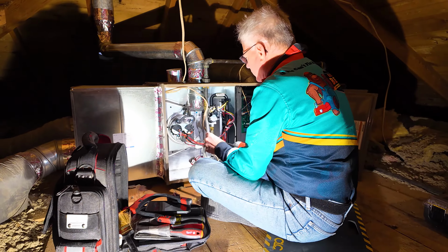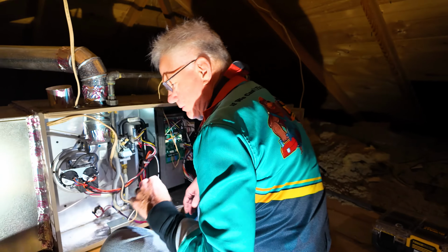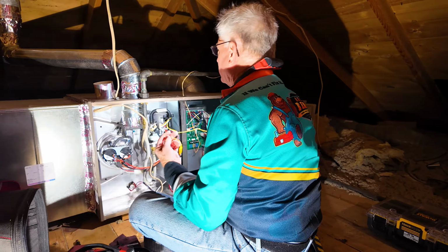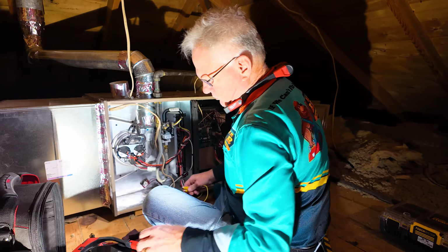Okay, so now I'm going to use a jumper like as if I turned the thermostat on downstairs. We'll see if it has a call for heat. I'm going to turn on the power to the furnace. And there's a safety switch right here, when you take the cover off, it won't run. So I have to hold that switch in. I have a magnet situation that I use here when I'm doing these, so I can put that on there. Okay, you hear it click. So we're going to see if it's got a call for heat. The board is initializing over here.